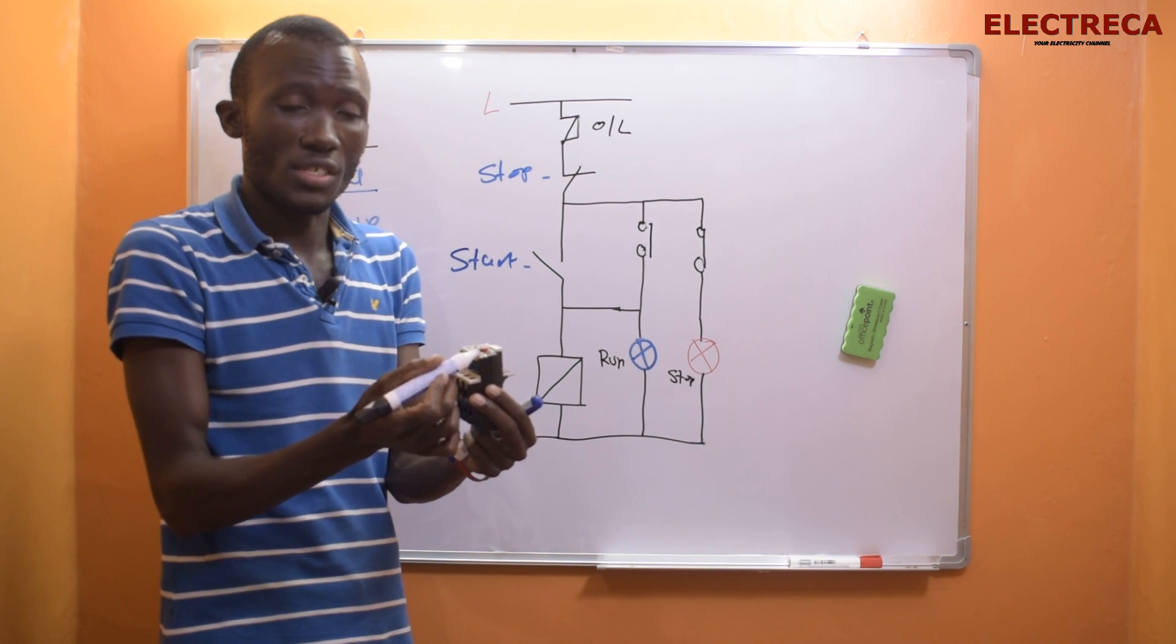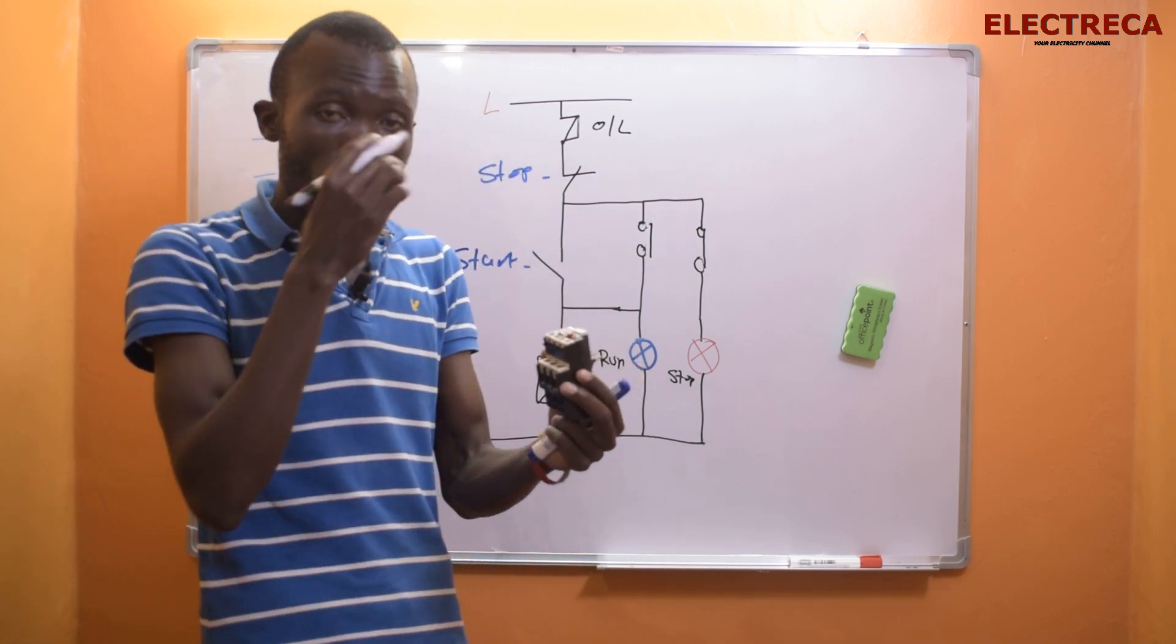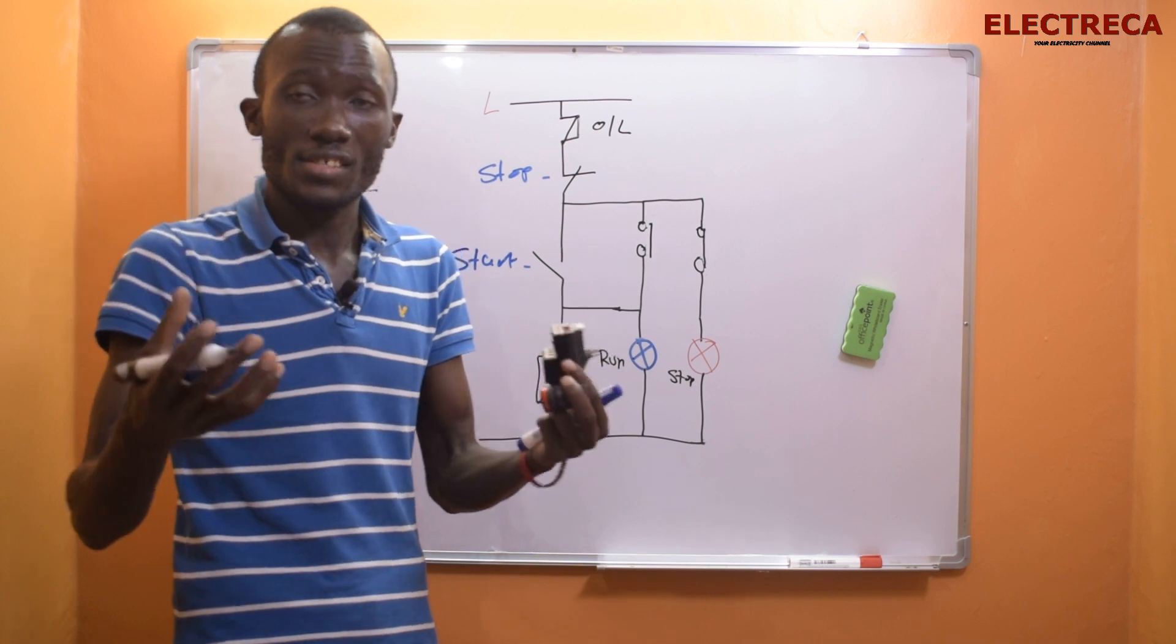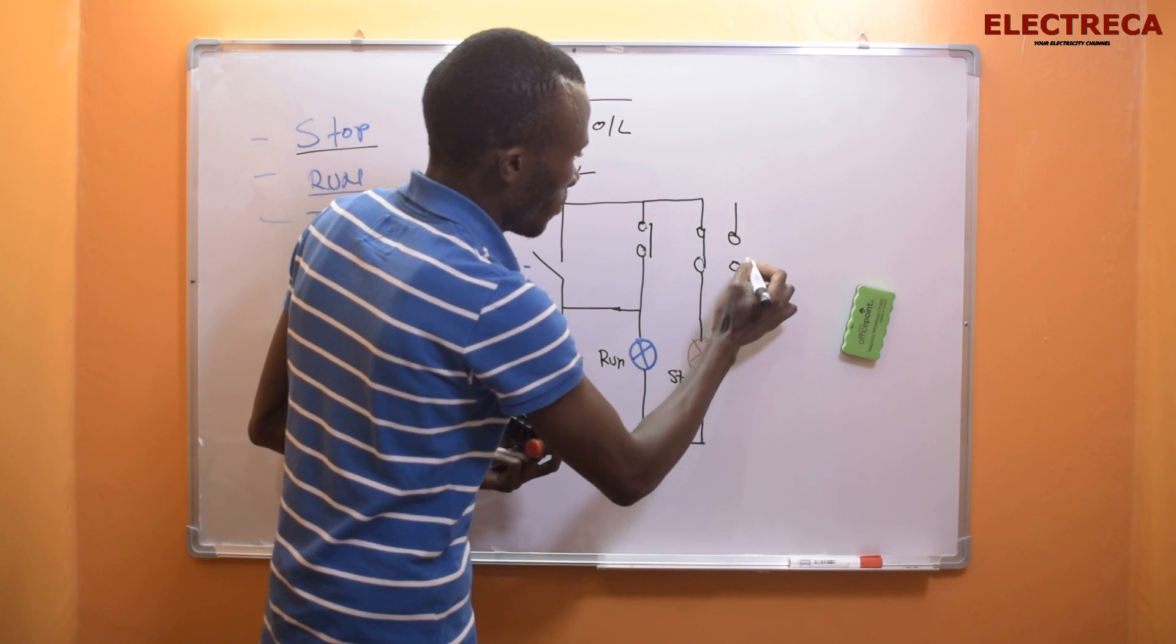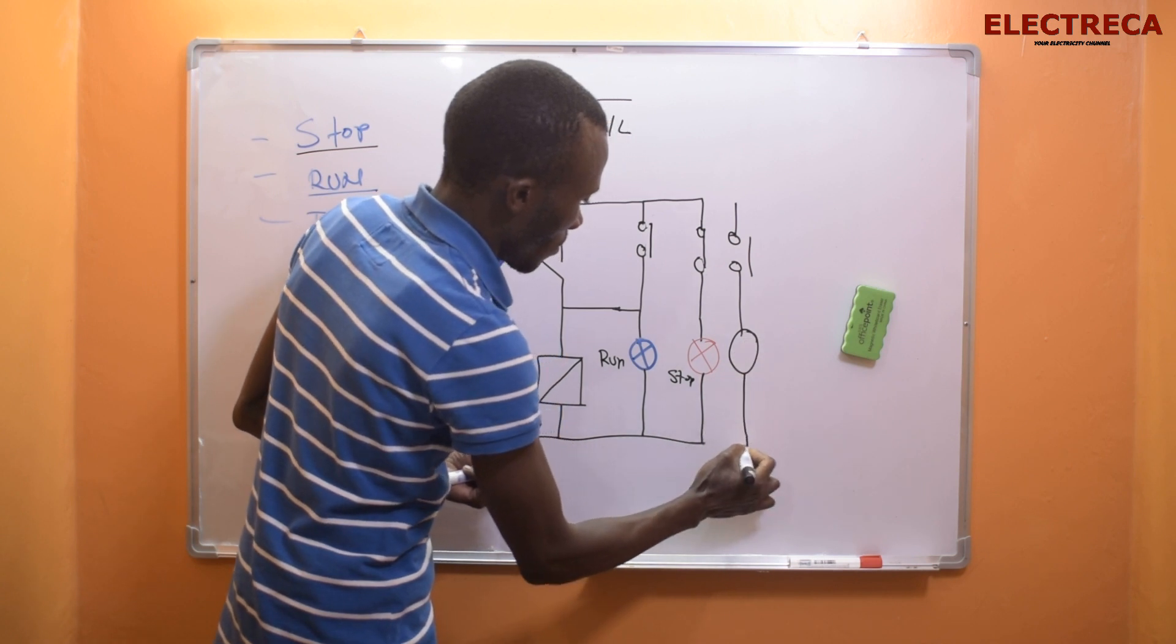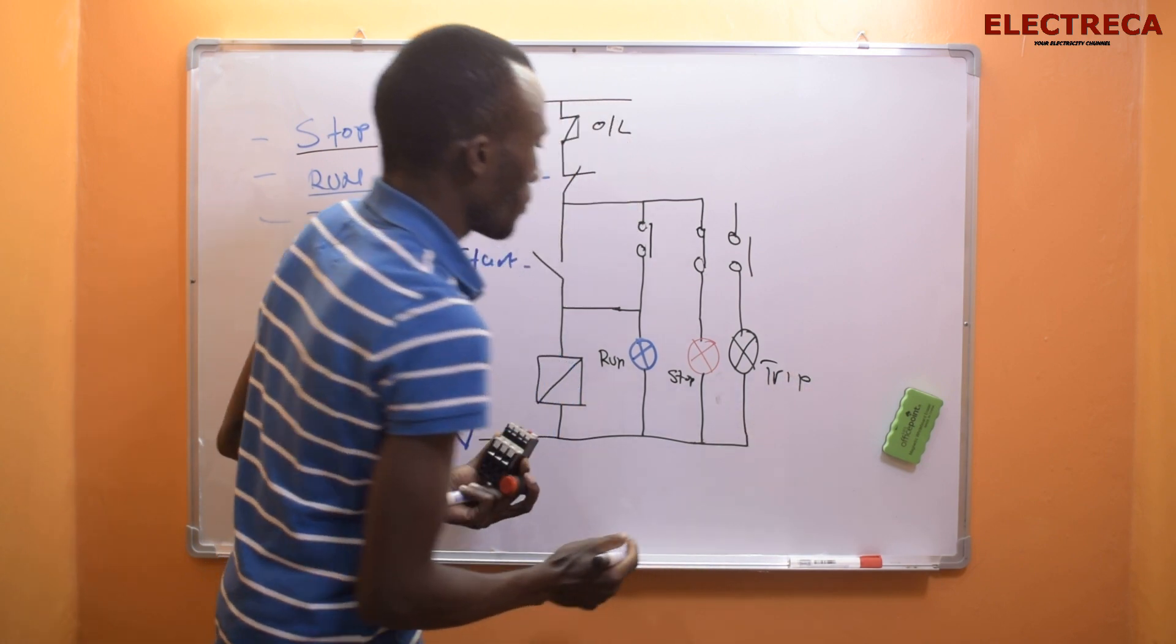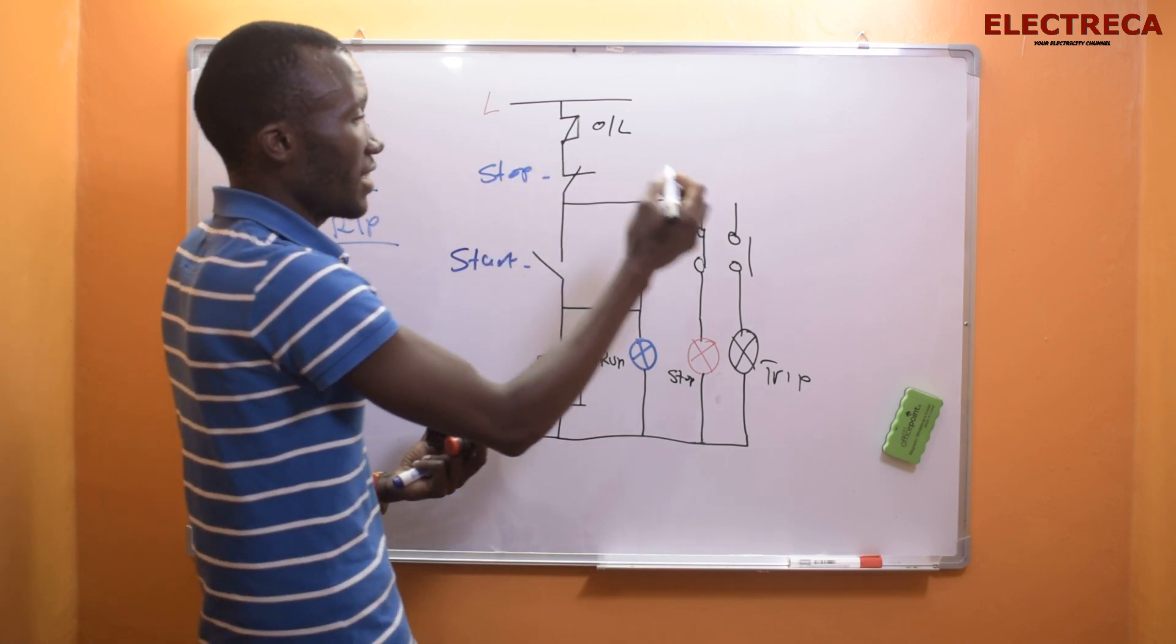The normally closed is where we connect our circuit, so through normally closed then to our stop. That means before the stop we have to go through the overload which is the normally closed contact, the 95-96. The other normally open is where we connect our indicator light which will show us that the circuit has tripped. We're able to add here, and this will be trip.